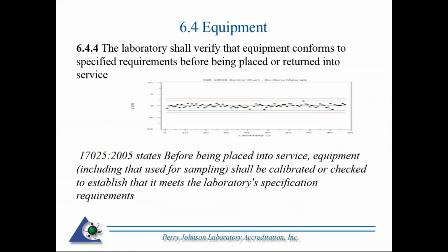Okay, 6.4.4, the laboratory shall verify that equipment conforms to specified requirements before being placed or returned into service. A little bit of change here. 2005 was very specific. It stated calibration. Equipment needed to be calibrated or checked to establish that it meets laboratory specification requirements. One thing that's been expanded, and we're going to get to that in a little bit, I don't want to put the cart before the horse here, is when does equipment need to be calibrated as opposed to checked or verified?